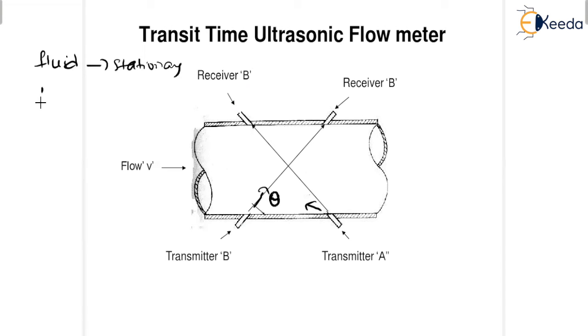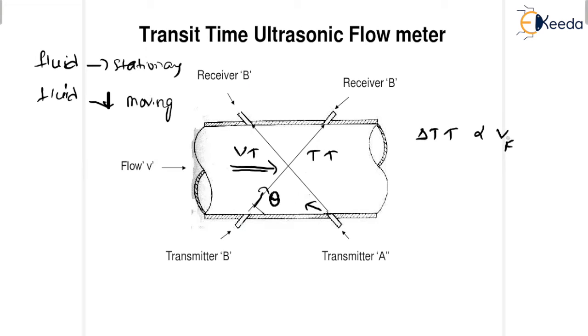Now the second time, the fluid is moving, my dear students. When the fluid is moving, there is a change. The velocity of the propagation of the sound changes, depending on the direction of the fluid flow. Therefore ultimately the time also changes, my dear students. And this change in time is proportional to the velocity of the fluid flow.